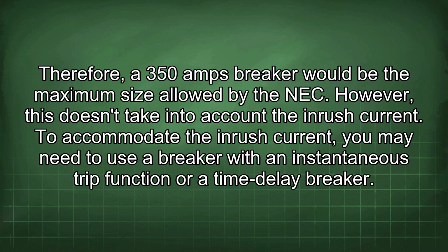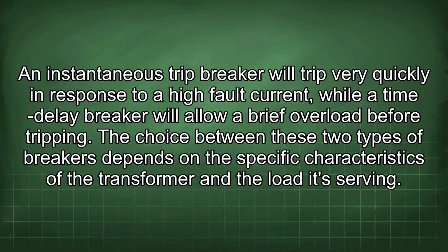However, this doesn't take into account the inrush current. To accommodate the inrush current, you may need to use a breaker with an instantaneous trip function or a time delay breaker. An instantaneous trip breaker will trip very quickly in response to a high fault current, while a time delay breaker will allow a brief overload before tripping. The choice between these two types of breakers depends on the specific characteristics of the transformer and the load it's serving.